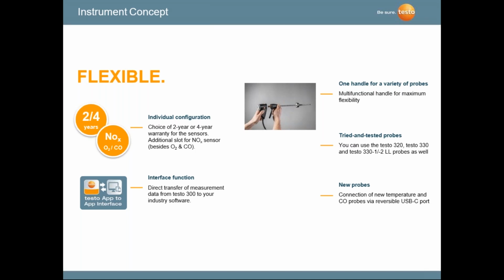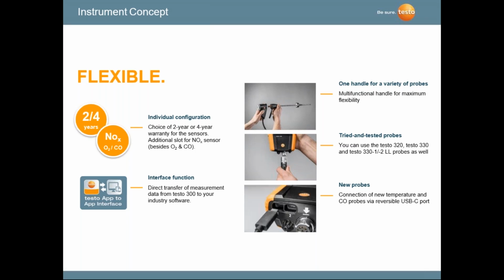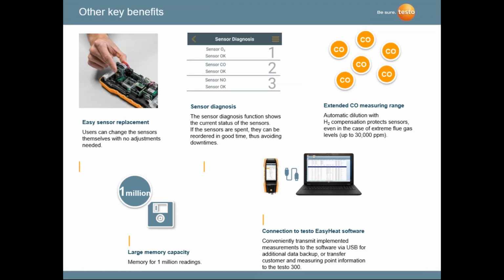If you're familiar with the previous models, we're still using the same probe and hose assembly. So it's a modular probe and hose assembly with one hose coming up. Internal to that hose is what we went through: the pressure hose, flue gas hose, and the thermocouple. Easily connected to the bottom of the instrument. You're not going to break any K thermocouple wires. You can tie a knot in this hose assembly and not break anything. It's a very durable probe and hose assembly, and that's why we stuck with it with the newer 300 models. And then you certainly have probes here, ambient CO probes and other probes that we talked about for adding additional capabilities to the instrument.